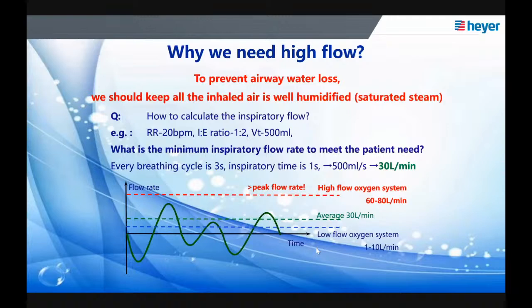So let's calculate. Every breathing cycle is 3 seconds, and the inspiratory time is 1 second. The tidal volume is 500 ml per second. So the minimum flow rate should be 30 liters per minute. But this is only the average flow rate. As we know, the patient's inspiratory flow rate has a peak flow. We need to meet the peak flow, so we need at least double the average flow rate. So the high flow oxygen system should have a 60 to 80 liters per minute flow rate.